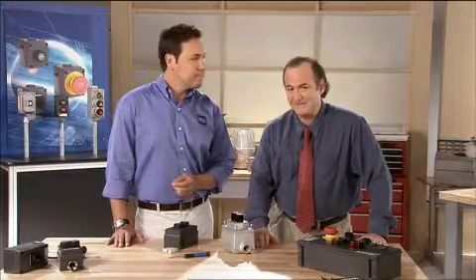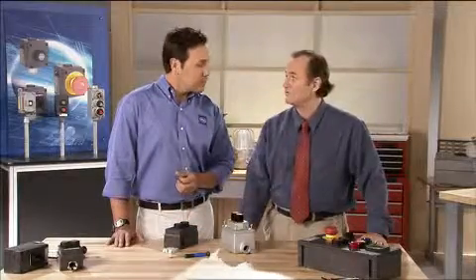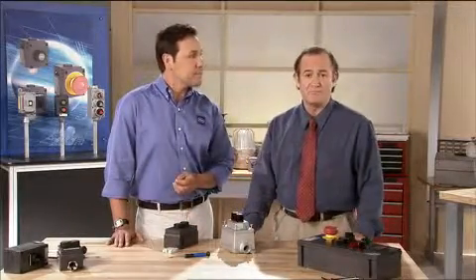Well, how does that affect safety? Well, Jim, one big safety lapse I've seen in the field is that once somebody finally gets all those bolts out and starts work, they may have to leave before the job's complete. Now, instead of replacing all of those bolts, only to have to remove them again when they get back, they'll just put the bolts in corners. They'll leave some of them out, or they'll hand tighten some of them. Boom, there goes your safety factor. Yeah, that's a catastrophe waiting to happen. But with the STAHL system, you can be done and closed up in about 15 minutes and move on.